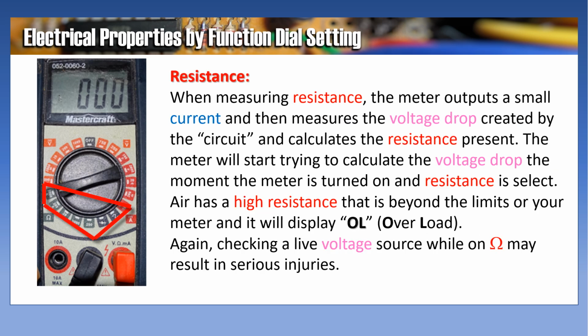When measuring resistance, the meter outputs a small current and then measures the voltage drop created by the circuit and calculates the resistance present. The meter will start trying to calculate the voltage drop the moment the meter is turned on and resistance is selected. Air has a high resistance that is beyond the limits of your meter, and it will display OL for overload. Again, checking live voltage source while on ohms may result in serious injuries.